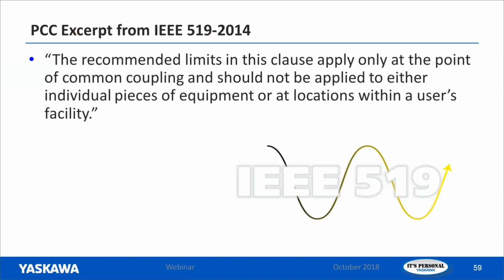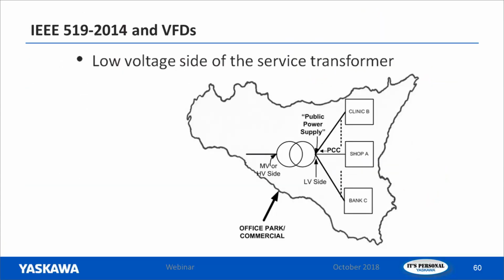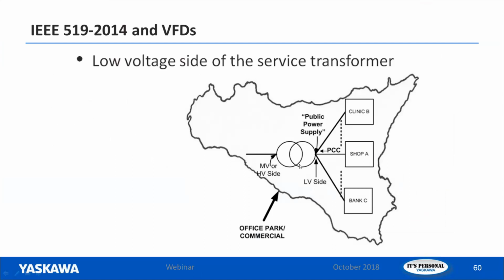Here's an excerpt from the 2014 document, and I'm just going to read this to you. The recommended limits in this clause apply only at the point of common coupling and should not be applied to either individual pieces of equipment or at locations within a user's facility. IEEE 519 really doesn't care what kind of distortion you're seeing at a particular point in a mechanical room or somewhere else. Here's a depiction of what the standard looks like now. I showed you what it looked like with the 1992 standard. Here's a better depiction now with the 2014 standard. What they're saying is, here's the public power supply, and they're feeding Shop A, Clinic B, and Bank C. Their main purpose is they want to make sure that the harmonic distortion that Shop A is feeding into the line does not affect the sensitive equipment that's over here running in Clinic B or in Bank C.